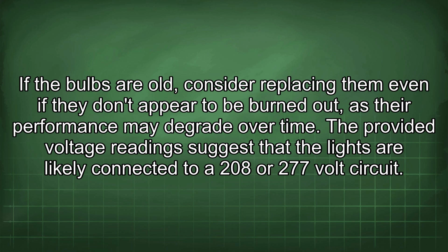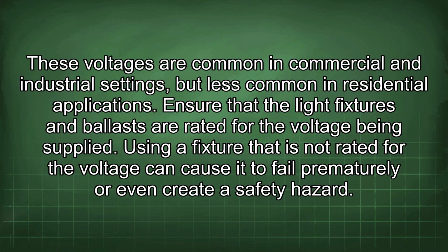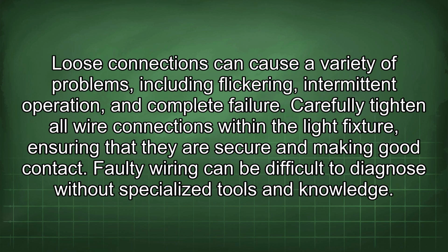may degrade over time. The provided voltage readings suggest that the lights are likely connected to a 208 or 277 volt circuit. These voltages are common in commercial and industrial settings, but less common in residential applications. Ensure that the light fixtures and ballasts are rated for the voltage being supplied. Using a fixture that is not rated for the voltage can cause it to fail prematurely or even create a safety hazard.